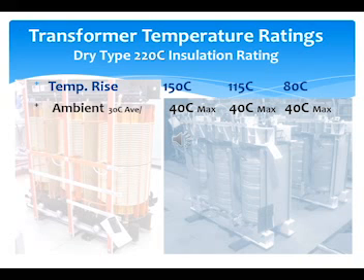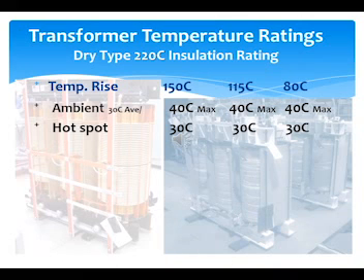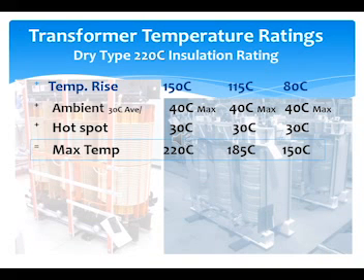Next we add the ambient, which is based on 30C average — 86F — over a 24-hour period, and 40C max — 104F — during that same period. Hot spot is a theoretical hot point inside the transformer, which is 30 degrees C added in. When we add these values together, we get the maximum temperature the transformer should ever see.